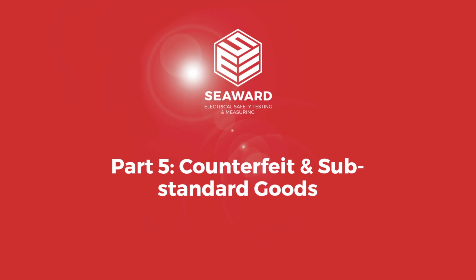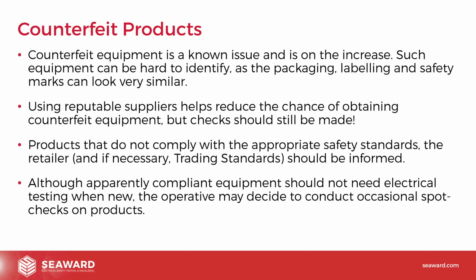Part 5, counterfeit and substandard goods. Counterfeit equipment is a known issue and is on the increase. Such equipment can be hard to identify as the packaging, labelling and safety marks can look very similar. Using reputable suppliers helps reduce the chance of obtaining counterfeit equipment, but checks should still be made. Products that do not comply with the appropriate safety standards, the retailer, and if necessary trading standards, should be informed. Although apparently compliant equipment should not need electrical testing when new, the operative may decide to conduct occasional spot checks on products.